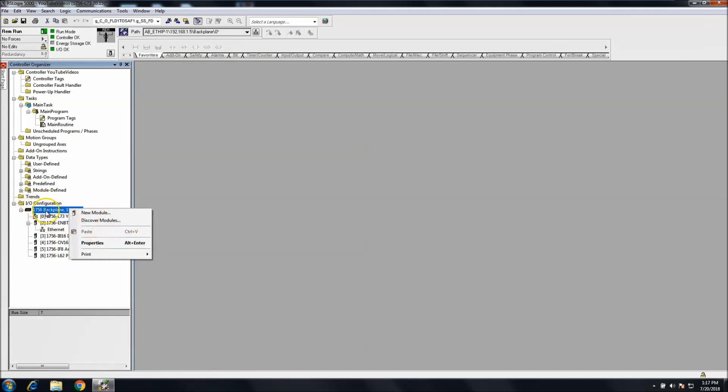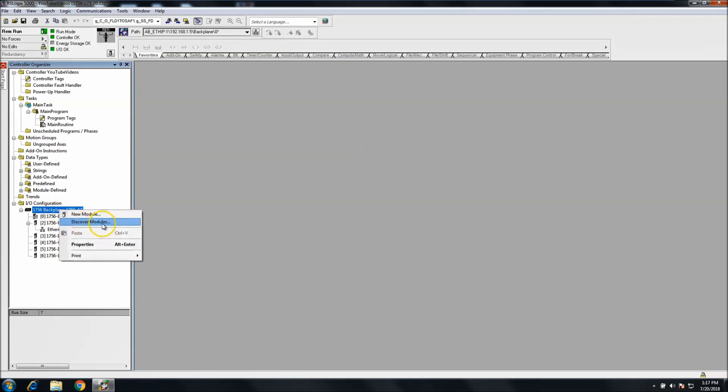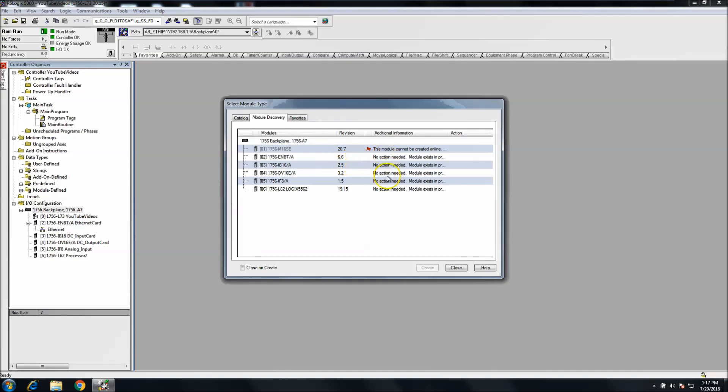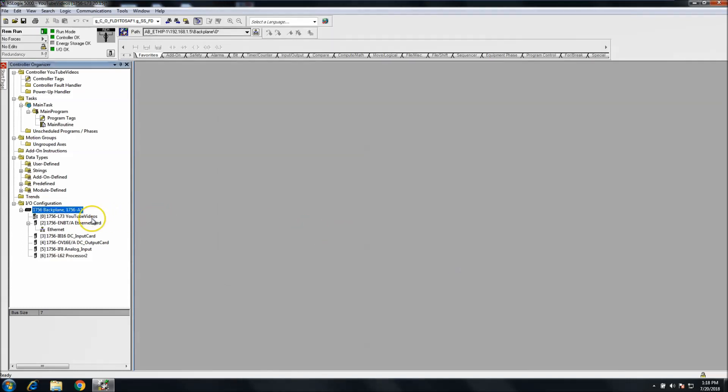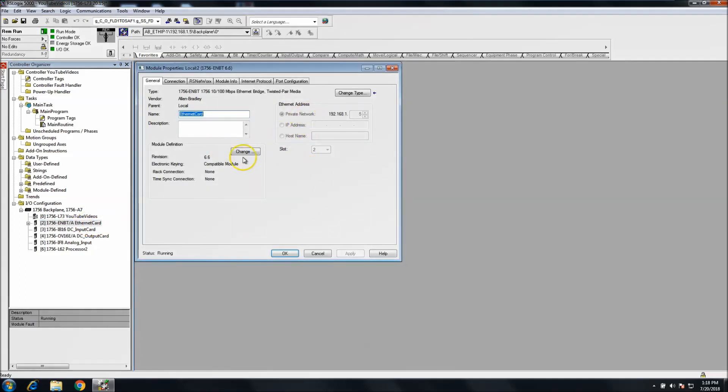Again, you always come down below your IO configuration in your backplane, you highlight your backplane, and you hit discover modules. When you hit discover modules, it's going to find everything it possibly can add. This saves you a lot of time if you already have a chassis that's preloaded and you have it powered up and you can communicate to it. Now, say for instance you don't have it wired up and you can't communicate to it, then you're going to have to pull the card and put in the information yourself. Obviously, if somebody's flashed the firmware, you'll have to understand what firmware it is.